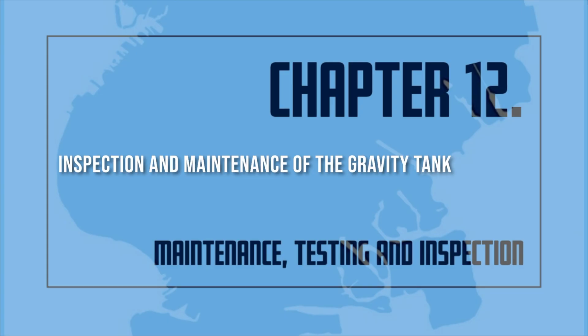Inspection and maintenance of the gravity tank. The gravity tank should be regularly inspected and maintained in accordance with NFPA 25, 2002 edition. Maintenance is needed to be sure that the tank functions correctly. Tanks are to be painted regularly to prevent rusting. Before the inside of a gravity tank is repainted, the surface should be thoroughly dried. All loose paint, rust, scale, and other surface contamination should be removed.